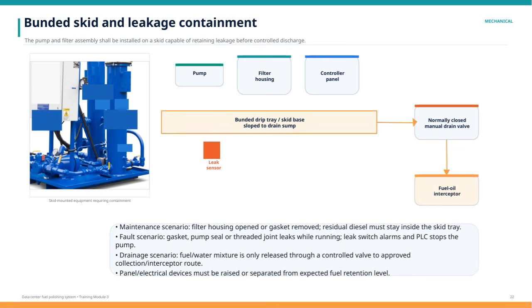The key idea is that the pump and filter must be installed on a skid designed to hold any leaks that may occur. This skid essentially acts as a containment area to prevent any fuel or fluid from escaping uncontrolled. The mechanical components mounted on the skid include the pump, filter housing, controller panel, and a bund drip tray or skid base. This base is sloped to direct any leaked fluid toward a drain sump. There's also a leak sensor to detect any unwanted fluid presence, coupled with a normally closed manual drain valve to control drainage. In terms of scenarios during maintenance, if the filter housing is opened or a gasket is removed, any residual diesel must remain inside the skid tray.